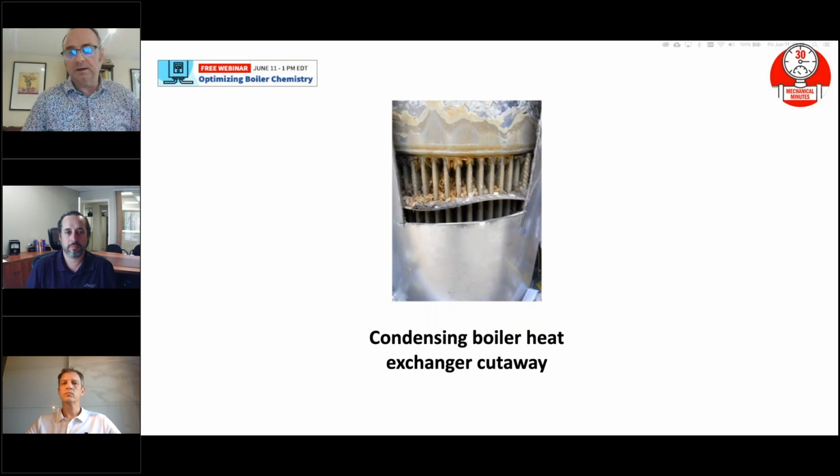So that's where I'm a big fan of what Brian mentioned: isolating your boiler system from your building. Putting a heat exchanger in between the boilers and your system enables you to have much better control over the boiler water quality. If you put a brand new boiler system in a retrofit building and take all the care in the world, you fill up that system, you flush your system, you fill it up with decalcified water, you test your water, your pH is good, everything's good, you flush it all out, you think you're good. Well, you've still got this massive building.